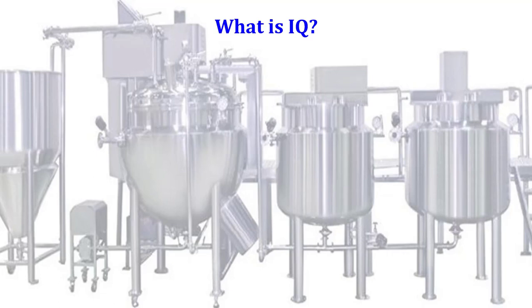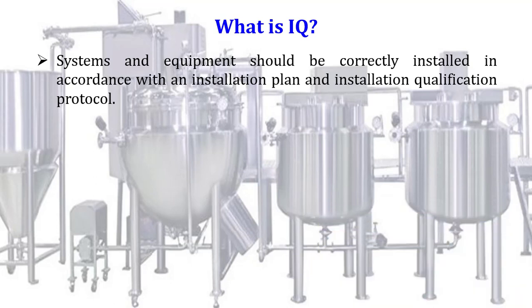So what is IQ or installation qualification? Systems and equipment should be correctly installed in accordance with an installation plan and installation qualification protocol. The system which we have procured should be installed at a particular location to perform or to use it for its intended use, commissioned or installed as per the requirements.